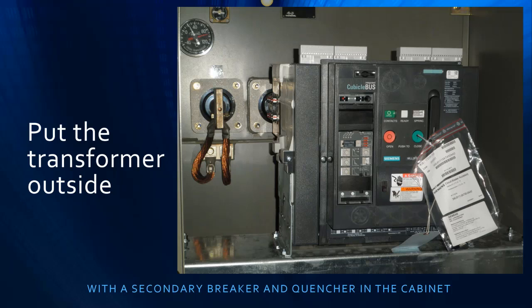Well, we configured the transformer bushings for just the right dimensions, so that they would match virtually exactly to this fixed mounted UL 1066 power breaker, which acts as the main for this switchboard. It's really a nice way to save space and save dollars. And the transformer manufacturer put the breaker in the cabinet and attached the bus bars to the bottom of the breaker so that they could terminate secondary lugs to that breaker.